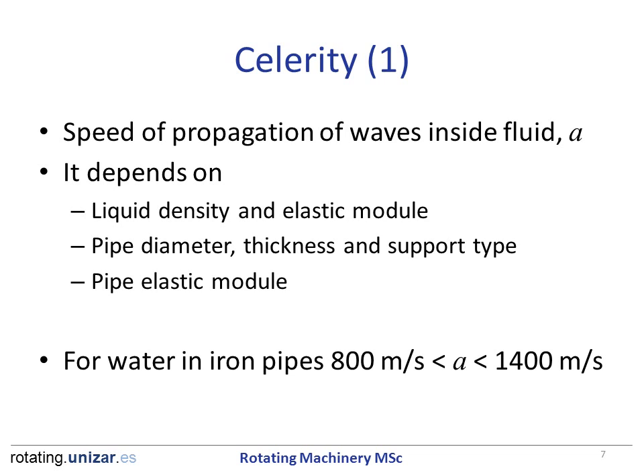The speed of propagation of waves inside a fluid is also called celerity. It depends on the liquid density and its elastic modulus, the pipe diameter, thickness, and support type, and the pipe elastic modulus. For example, for water in iron pipes, it is something between 800 meters per second and 1400 meters per second, depending on the pipe characteristics.